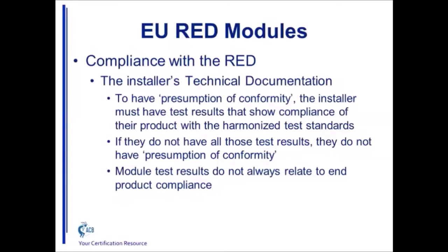And it really requires understanding how the device is going to be used. The manufacturer should have a good understanding of the end use and what the typical applications may be in order to make a proper assessment of those end tests. So we may choose not to perform a lot of the radio tests if we have sufficient documentation from the radio module manufacturer that the device complies with the necessary requirements.